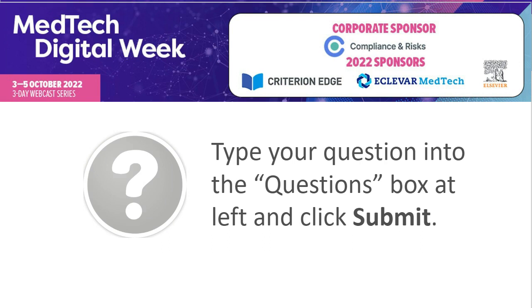safety and performance objectives that your competitors are reporting on and that you report on, or most importantly, that you have data for. We talked to some of our clients that are very concerned about data sufficiency, and they have very little data on their devices. So for what data you do have, you should design your safety and performance objectives around it, as long as it's meaningful data. I'll say that caveat. But if you have some meaningful data on your device, make sure your safety and performance objectives match those data. Because you can't put extra data in the CER that you don't have safety and performance objectives for. All data sets presented in the CER, PMS, PMCF, clinical investigations, published data on your device, all those data sets are going to be compared to your safety and performance objectives. So choose wisely.